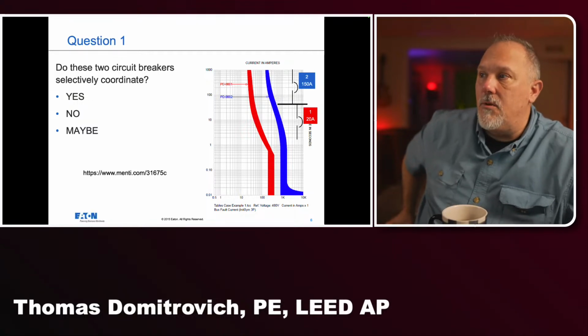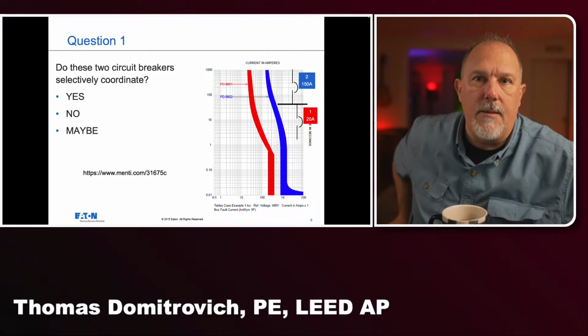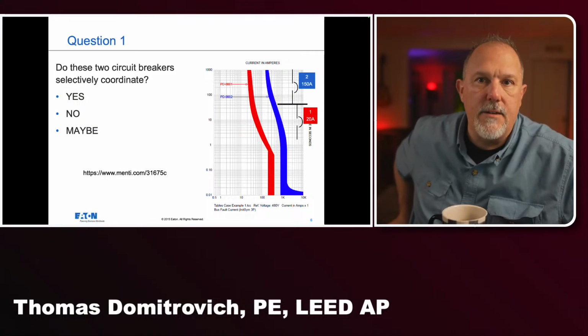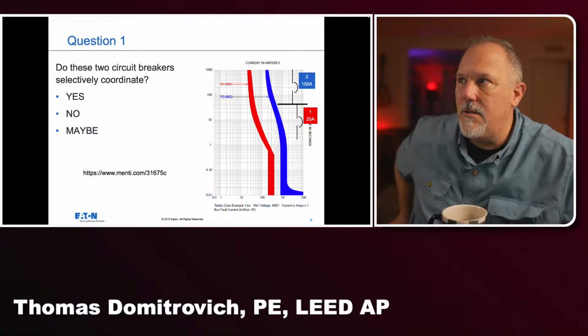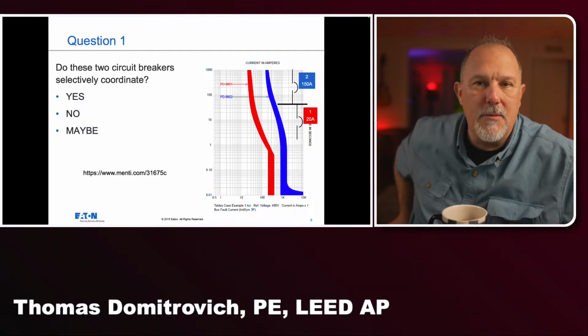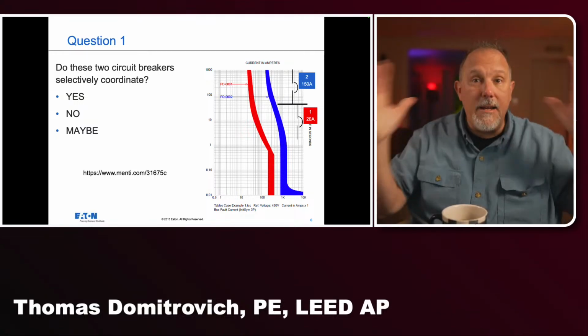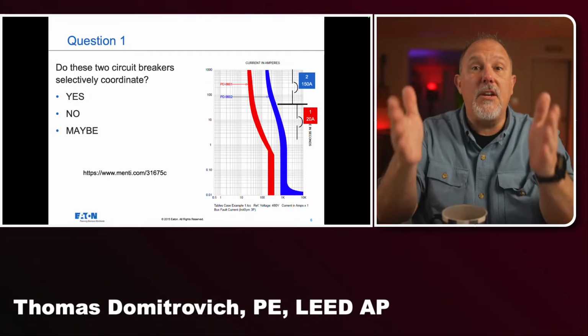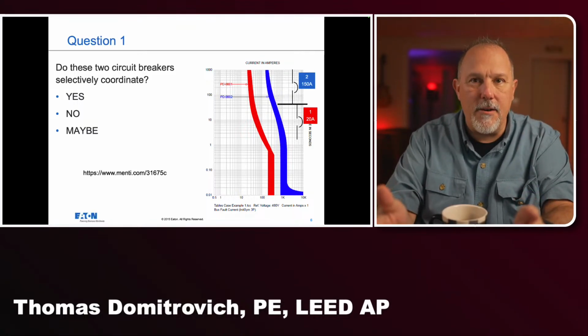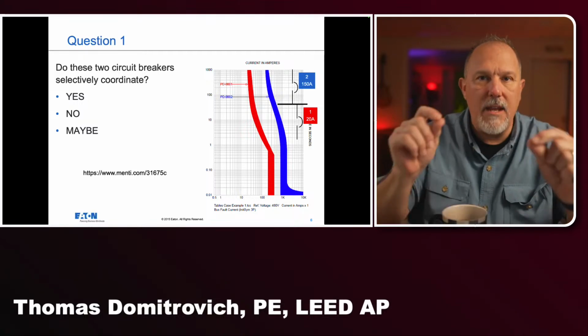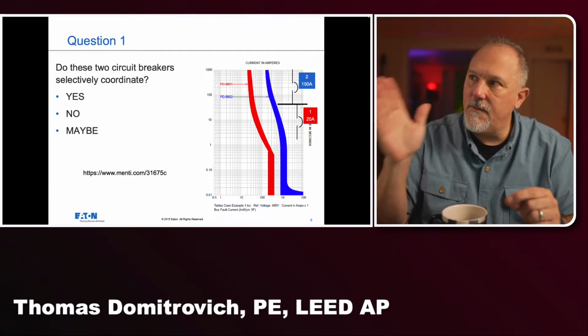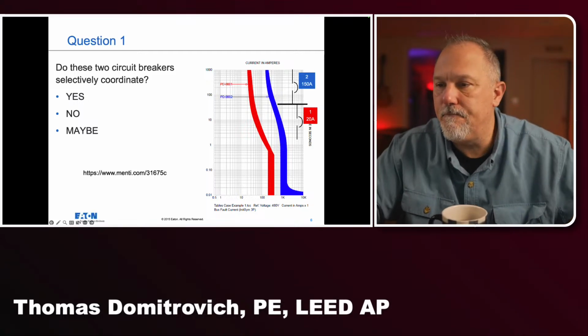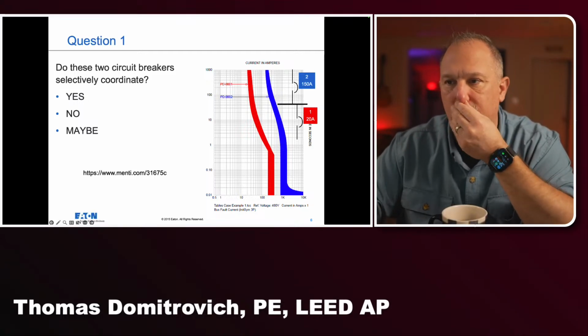The individual said, okay, well, 10,000 amps. And I said, oh, well, if it's 10,000 amps flowing through both of those breakers, what do you think is going to happen? And there was a long pause on the phone. And the individual said, they're both going to open. I said, right. Is that selectively coordinated? And it was like a light bulb going off in that person's head, because I know they know better. But when they look at those curves, they make the assumption that that breaker is not getting cut off. All right, let me keep going here.